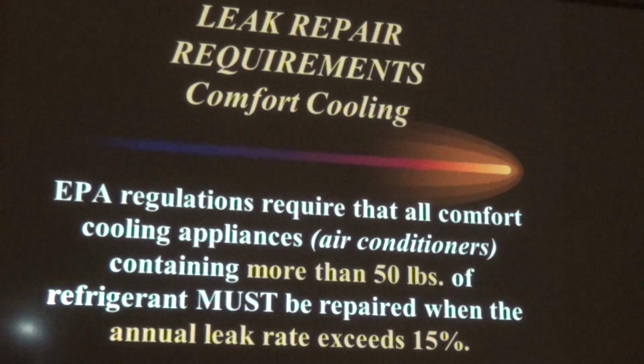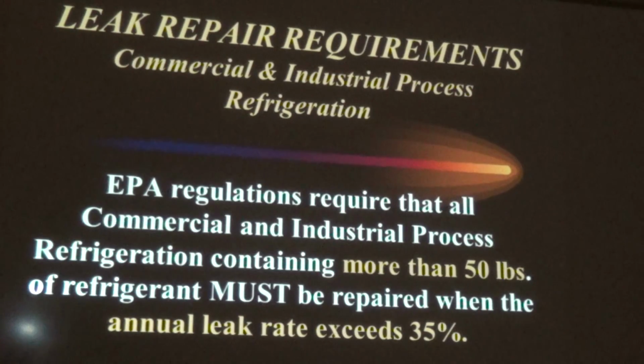So, if you have a system that has less than 50 pounds, the law doesn't apply. If you have a system that has more than 50 pounds, the law will apply. If it's a house air conditioner system, it can't leak more than 15% a year, so it can't lose more than 7.5 pounds. The next one has to do with commercial leak requirements, commercial and industrial. The EPA requires that if you have a commercial or industrial system, more than 50 pounds, the leak rate is a little more forgiving. It goes up to 35%. So for air conditioning, it's 15%. For commercial, it's 35%. In both cases, there has to be more than 50 pounds of refrigerant.